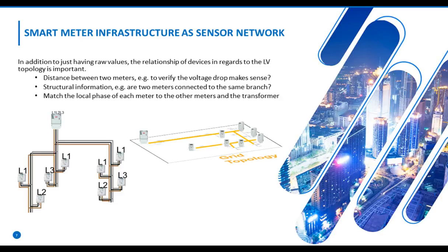And actually, this cable going to the line 1 terminal, line 2 terminal, line 3 terminal corresponds to the terminal at the transformer, which then allows us to aggregate across feeder lines and say, okay, we see on this feeder, for example, as I said before, the voltage drop between L1, which might be a different terminal, on one meter, and L1 on the last meter's line, and can really tell the DSO, okay, we see a true phase model overlaid with data to give you much more information than before. So what you can actually do with this information is another thing.